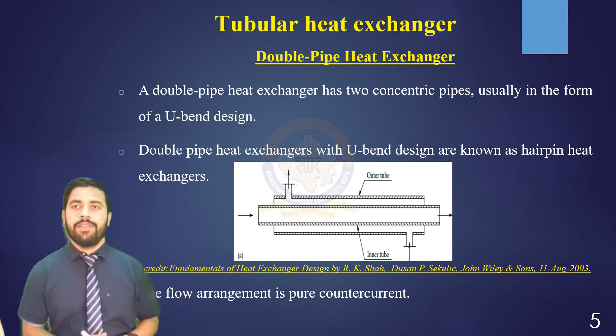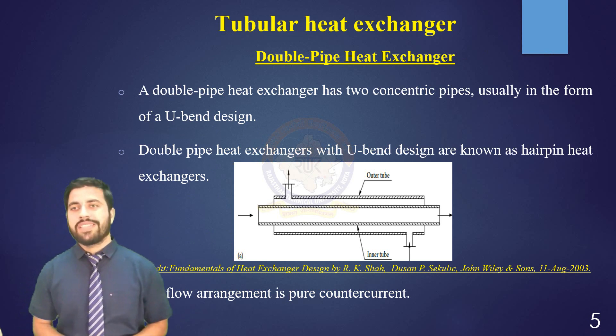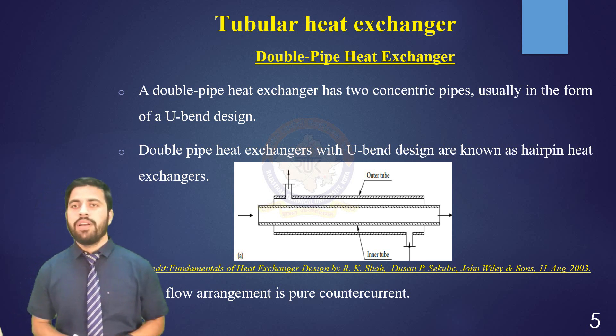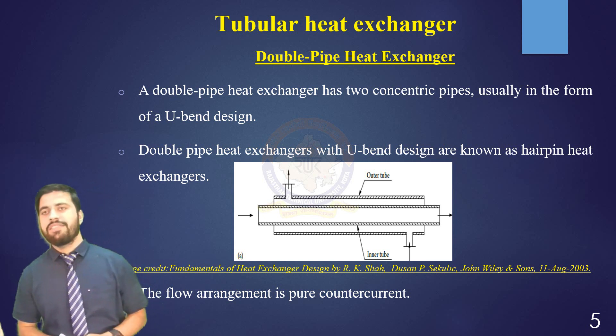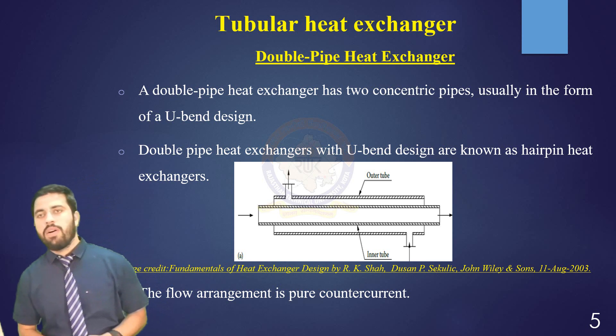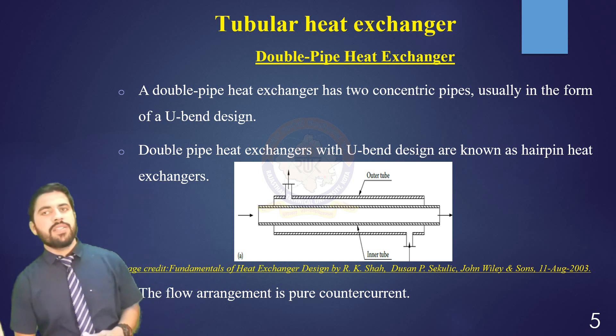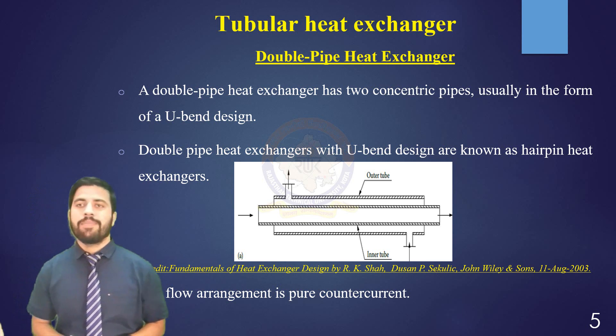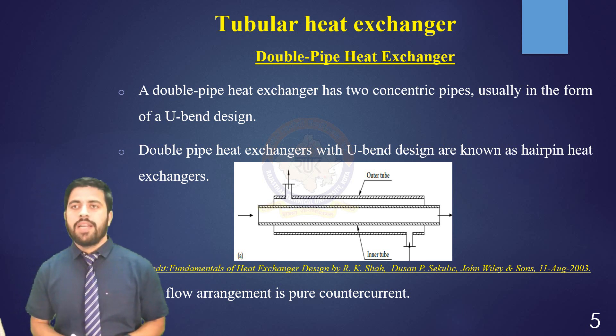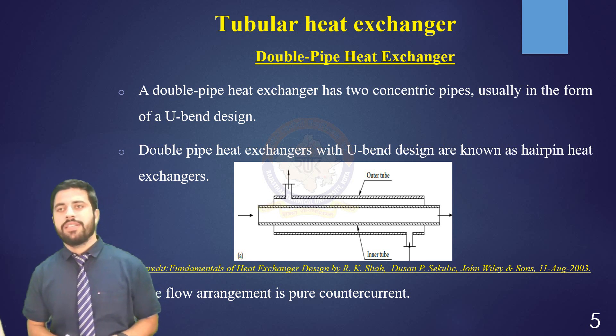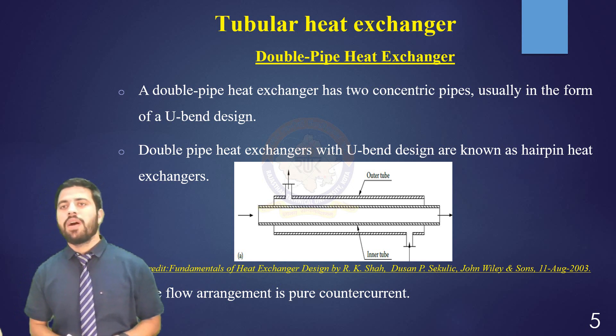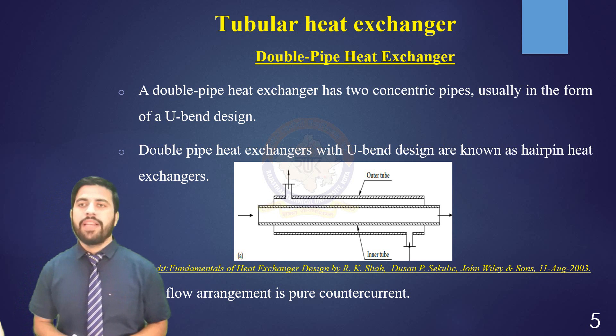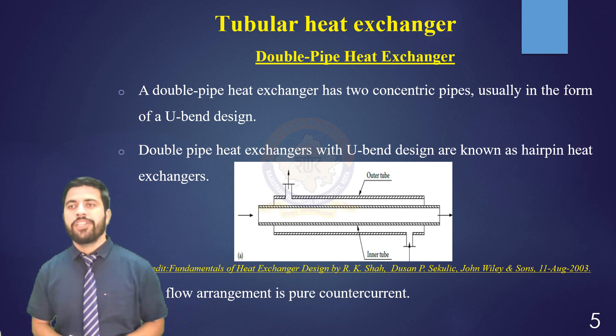Coming to the first category of classification, which is according to the basis of construction: heat exchangers are classified as tubular heat exchangers, which include double pipe, shell and tube, and boiler tube heat exchangers; plate type heat exchangers; and extended surface heat exchangers like tube-fin or plate-fin heat exchangers. A double pipe heat exchanger has two concentric pipes, usually in the form of a U-bend design. Double pipe heat exchangers with U-bend design are known as hairpin heat exchangers. The flow arrangement in this type is pure counter current, and they are suitable for small duties, high pressures, and temperatures.